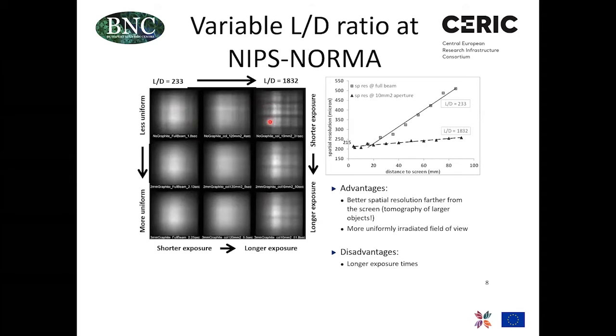Due to the properties of the neutron guide, the raw image after a neutron guide always shows some kind of stripe structure, but this is very unpleasant for imaging purposes. Our goal is to have something like this, which is quite flat and smooth. And this you can achieve by changing the collimator sizes and installing different thicknesses of graphite scatterers upstream into the beam.